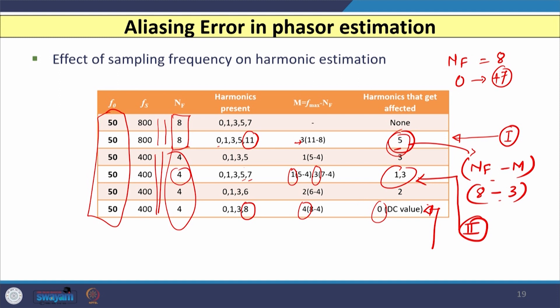In summary, whenever higher-order harmonics greater than NF are present in the acquired signal, their effect is reflected on the estimation of other harmonic components. In this class we covered: how to calculate the weight matrix (CW and SW), how to compute ICW and ISW, how to estimate phasors for DC, 1st, 3rd, and 5th harmonics, and the important aliasing error effect — where harmonics greater than NF corrupt the phasor estimates of lower-order components. Thank you very much.